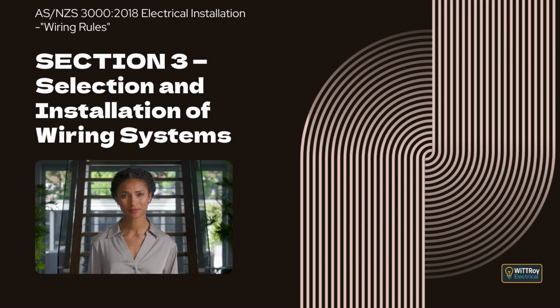Clause 3.3.2.11 Solar radiation, direct sunlight. This clause explains that where wiring systems may be exposed to direct sunlight, they must either be suitable for those conditions or be adequately shielded. Sheathed cables exposed to sunlight generally do not need extra protection from ultraviolet radiation unless the manufacturer advises otherwise. Black insulated unsheathed cables with ultraviolet-resistant insulation that complies with AS/NZS 3008 do not need extra protection. For other insulation colors, the manufacturer's advice should be followed or a physical barrier provided. Direct sunlight can affect current carrying capacity, and a correction factor may be applied where the cable temperature is higher than ambient.